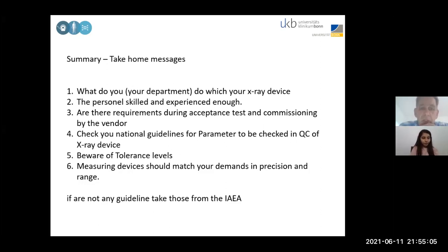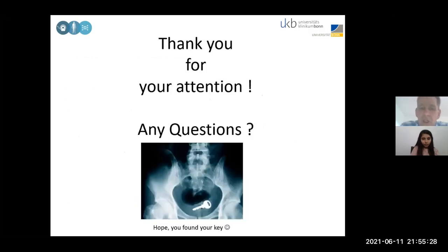And the measuring device should also meet the demands and precision of the range you're working in. So if you measure from 30 kV up to 120 kV, make sure your equipment measures this range and not only at 70 kV. And if there are no guidelines, I recommend going to the IAEA. They usually have guidelines which guide you. So thank you for your attention. Now I think it's open for questions, and I hope you found your key.